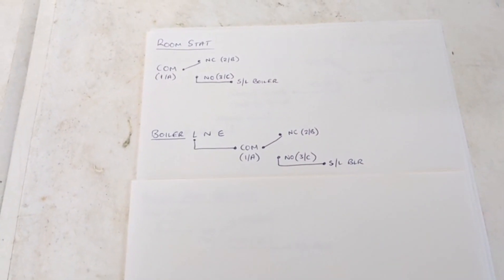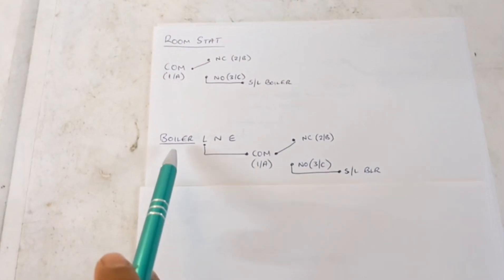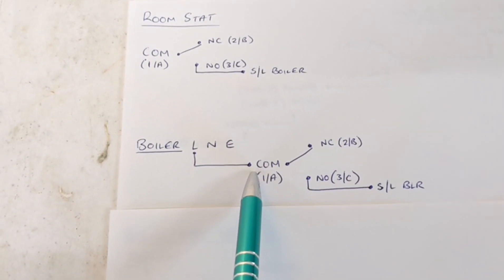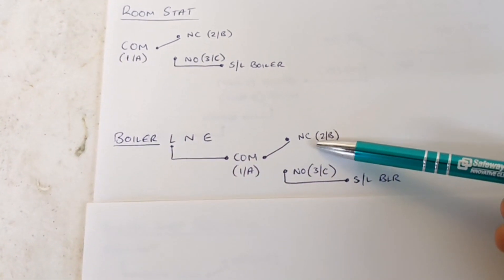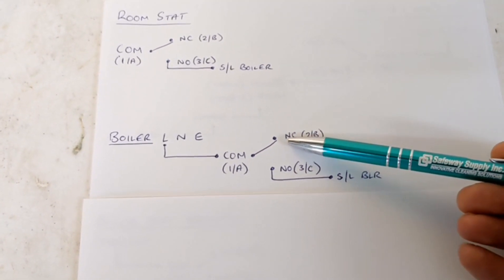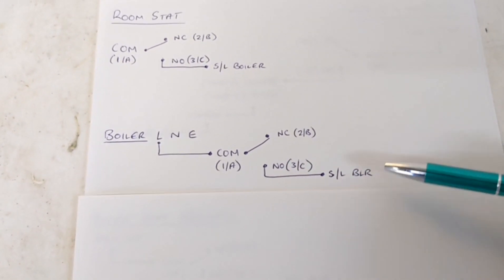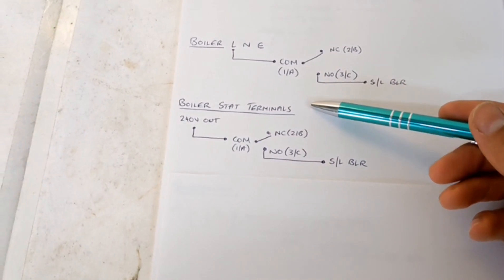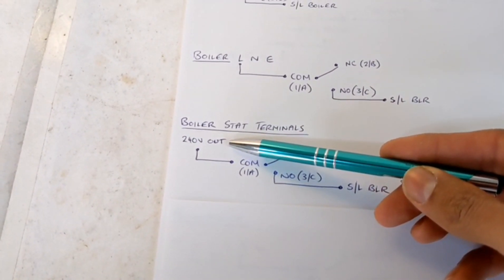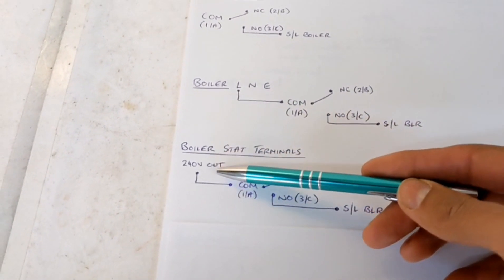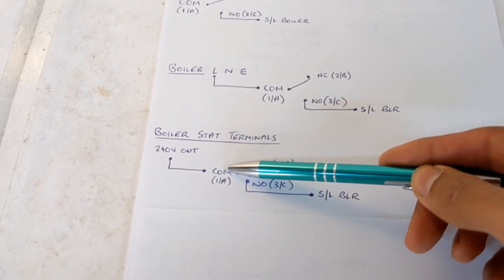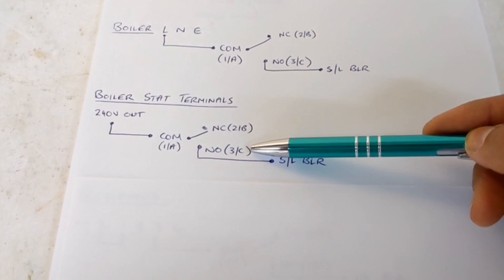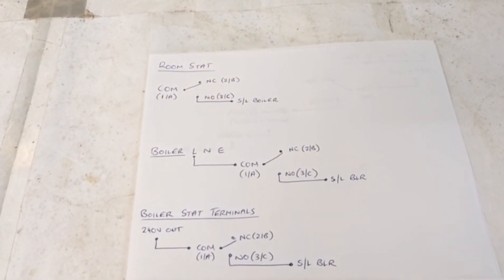Next up is how do you get power to the common. With a combi boiler you're going to have your live, neutral, and earth — you can piggyback off the live in the boiler and that goes to your common on your room stat. At rest with no demand it will be sitting at normally closed. When you turn the room stat up and hear that click, that's gone over to normally open — the switch live on the boiler — and the boiler fires up. Some boilers will actually have stat terminals with a dedicated 240 volt output, so you don't have to piggyback off the live. Same thing applies: goes to common, sits at normally closed at rest, flicks to normally open on demand, and goes to the switch live on the boiler.